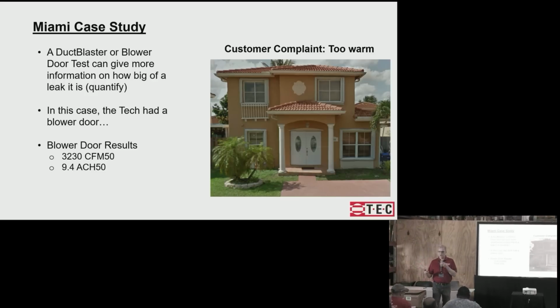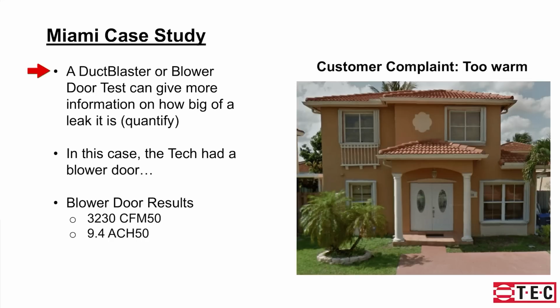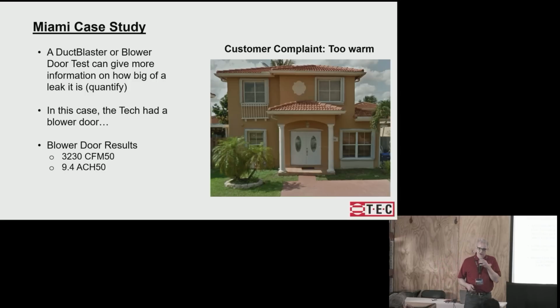So to know how much leakage you have, the next step has to be a blower door or a duct blaster test, which can help you find out how many CFM are leaking out of the system. And in this case, the technician did a blower door test, and he measured 3230 CFM, which is 9.4 ACH 50. Okay, that's not a very tight house. That's pretty leaky, but it's also pretty typical of this age house in Miami. So not a good number, but not really the reason that the system is not keeping up, especially because the technician put this leakage into the Manual J calculation, and so the Manual J is accounting for this much leakage under normal conditions.